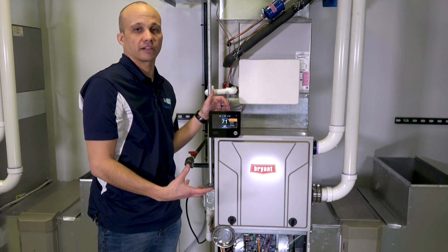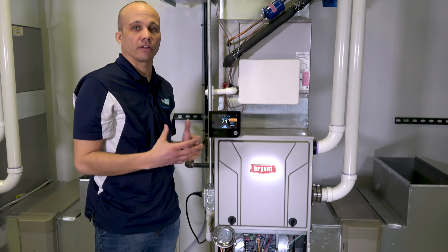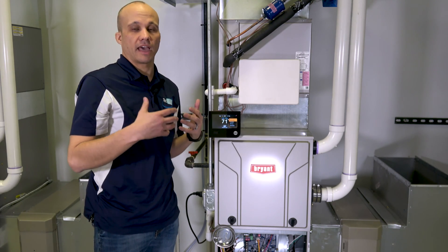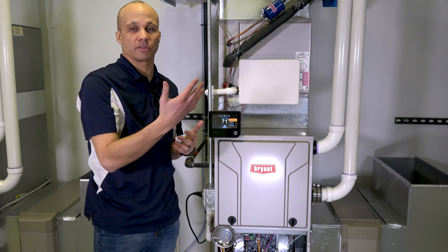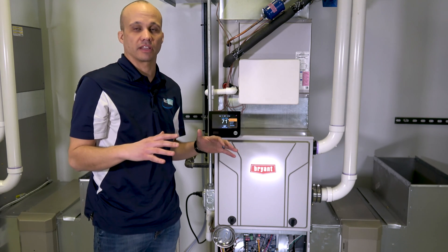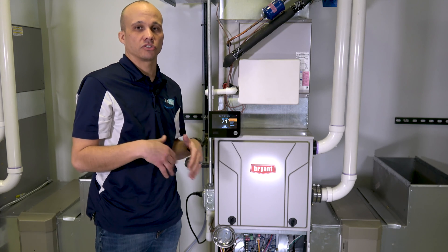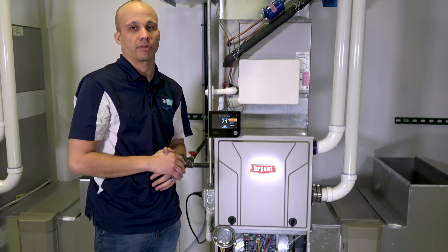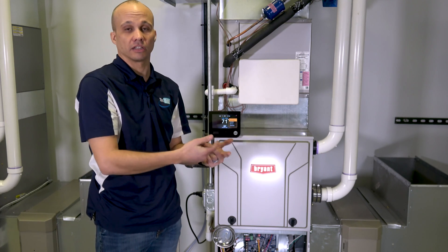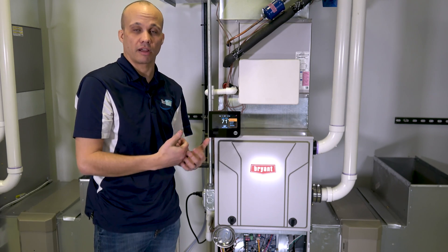So the purpose of having this smoke detector, if I have a fire anywhere in the home, anywhere at all, that air is going to get sucked back into the return of my system at some point. And I can detect that with this duct smoke detector and shut everything down. We don't want to use the duct system to continue to distribute smoke throughout the rest of the house. Right? Shut it all down and stop that process. And then additionally alert the customer in case they were not home or whatever.